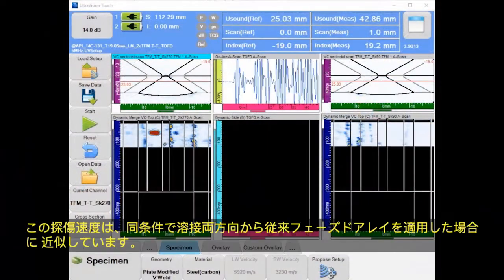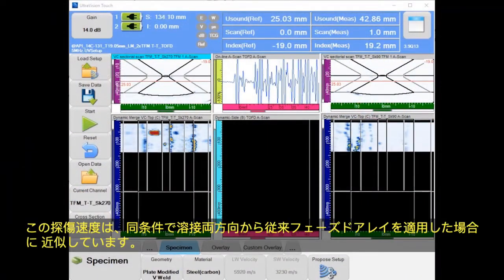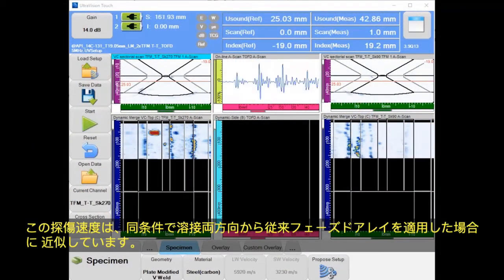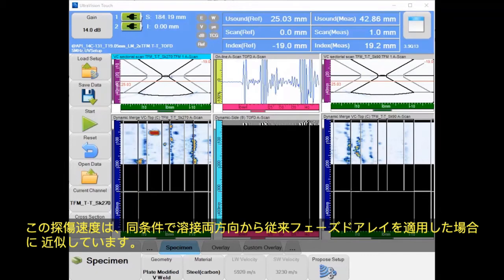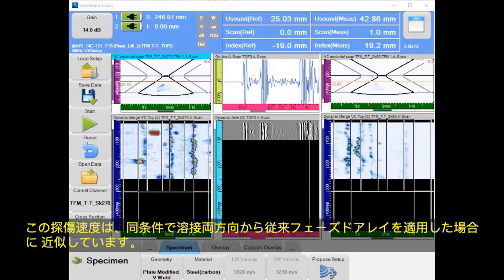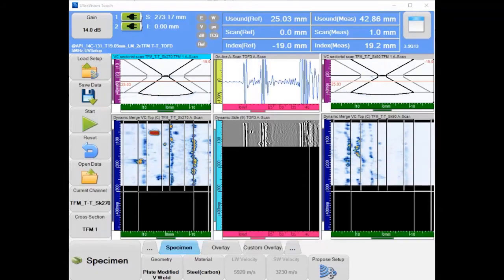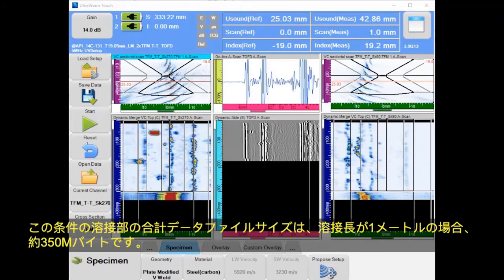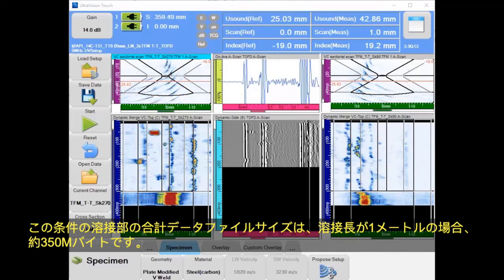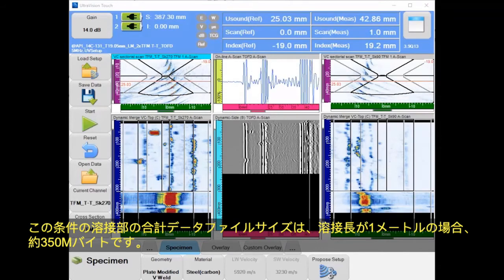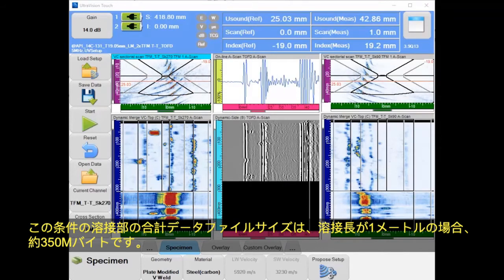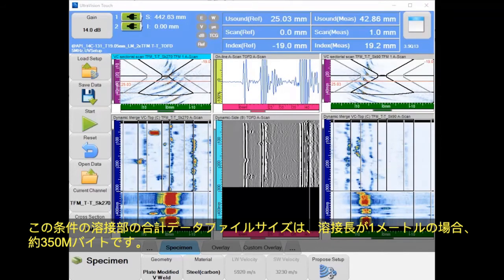This speed is very similar to two-sided standard phased array with similar inspection parameters. The total data file size for this type of weld is around 350 MB for a weld length of 1 m.